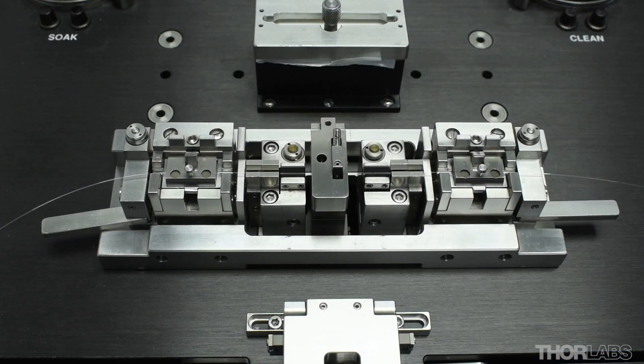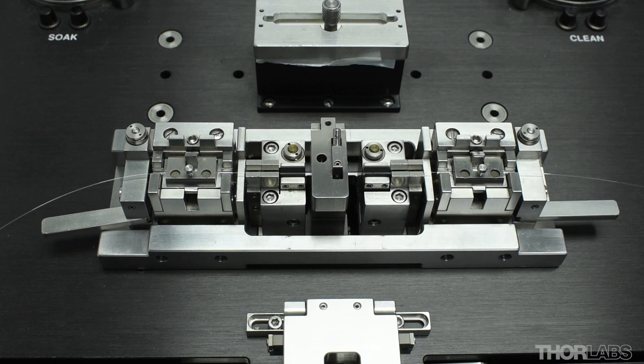To carry out a splice, first ensure you have two stripped, cleaned and cleaved fibers loaded into the left and right hand sides of the splice station.